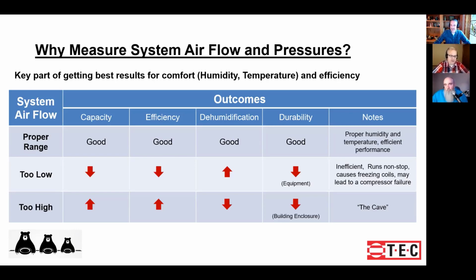And I've heard Ed call this situation the cave. You got a big system. You can get the set point down to whatever temperature you want, but it's going to be damp and humid, just like you're in a cool, damp cave. Yeah, that doesn't sound so good. What happens fairly frequently is somebody goes from an older piece of equipment where we had a coil that was starting to get dirty, maybe a fan that wasn't as powerful, but the system ran a real nice, low sensible heat ratio. It was doing a lot of dehumidification. Then a brand new high efficiency system gets installed. And unless the airflow is set up properly, you're going to have the exact scenario that Steve is speaking about.